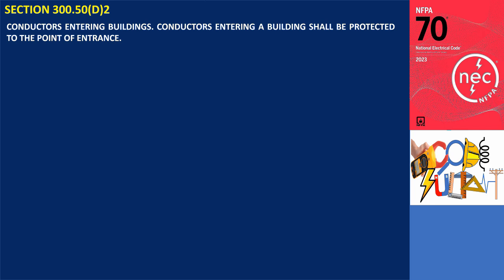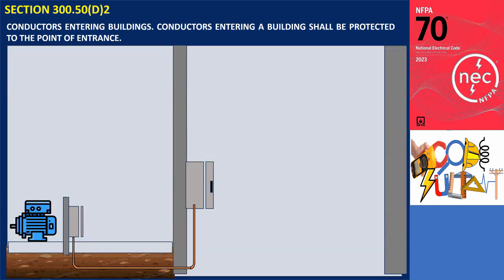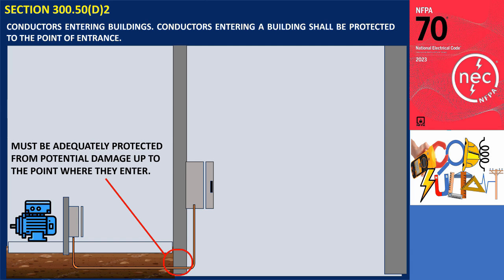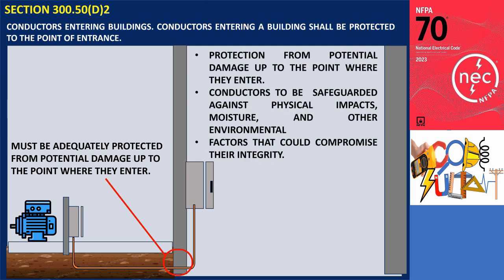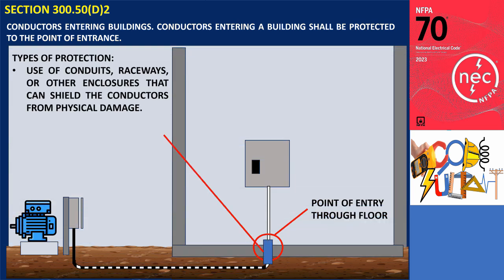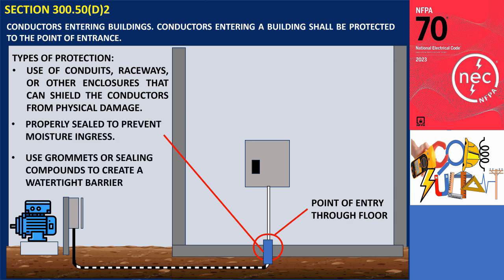Section 300.50(D)(2) addresses the requirements for protecting conductors as they enter a building. The conductors entering a building must be adequately protected from potential damage up to the point where they enter. This ensures that the conductors are safeguarded against physical impacts, moisture, and other environmental factors that could compromise their integrity. The point of entrance refers to the location where the conductors transition from an outdoor environment into the building's structure — through walls, floors, or other structural elements. Common methods of protection include the use of conduits, raceways, or other enclosures that can shield the conductors from physical damage, and the entry point must be properly sealed to prevent moisture ingress.